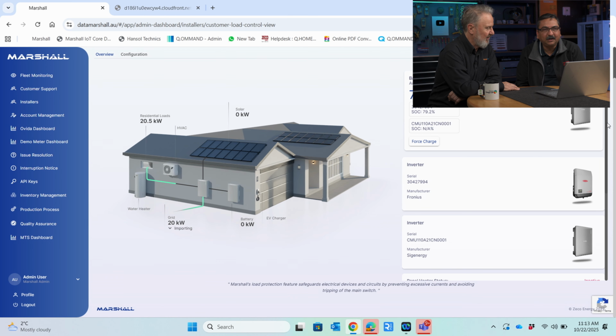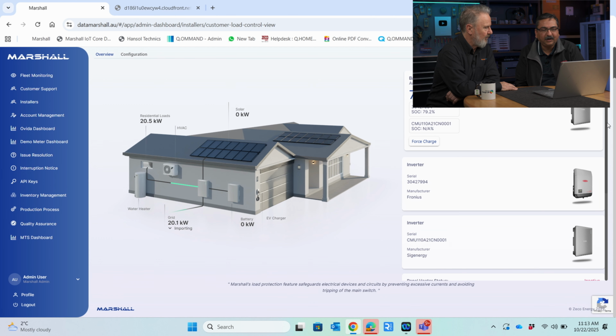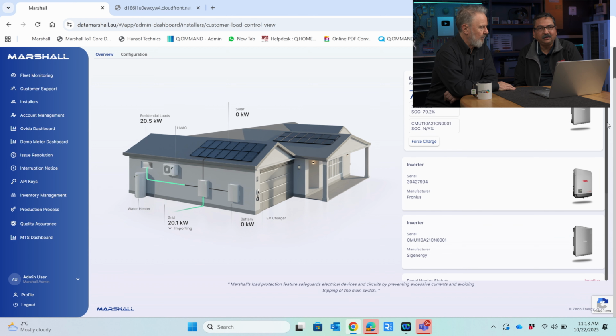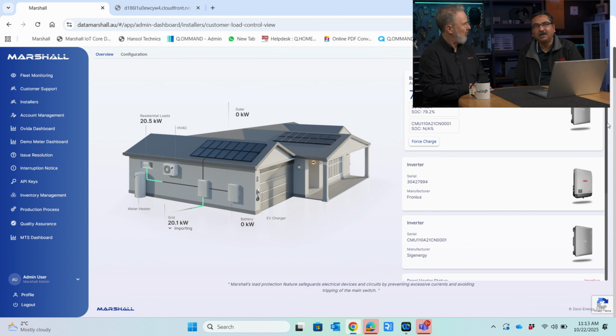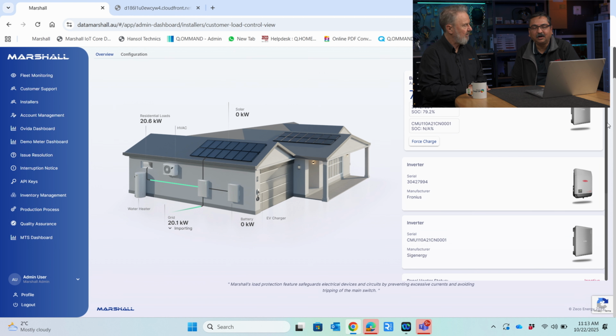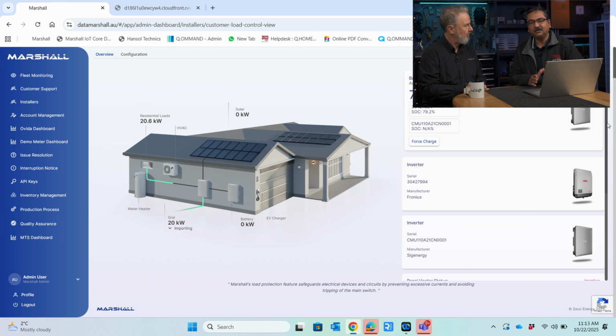That's the load application. There's one more circuit we control where if any energy is fed into the grid, any exported power, we turn on a load to absorb that power. In your case, we turn on a big load to keep the frequency under control, because it's a mini grid. You want to control on frequency, not on export. So we do that. That was the basic application of Marshall at your site, a load control box.